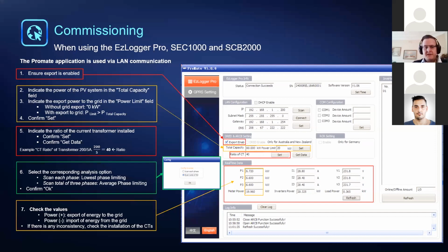Below that, we'll find our CT ratio. The CT ratio is the calculation of the transformer size. So if it's a 200 to 5, we take 200 divided by 5. That will give us 40, which is our CT ratio. So we just input that, hit the set button. After pressing the set button, we're going to select Get Data.